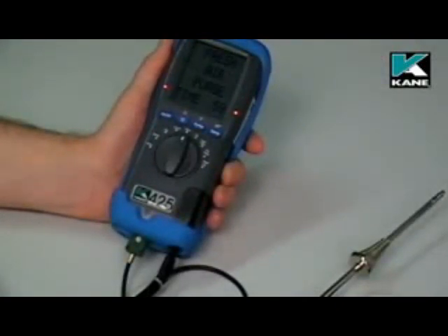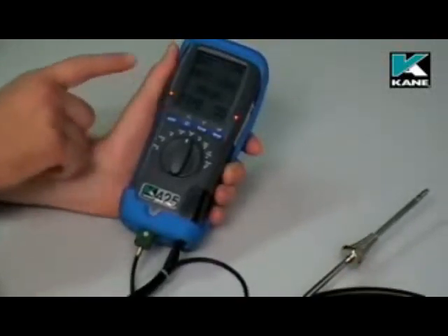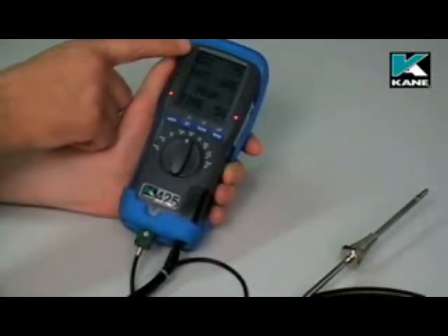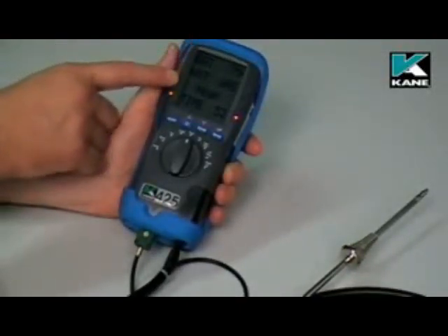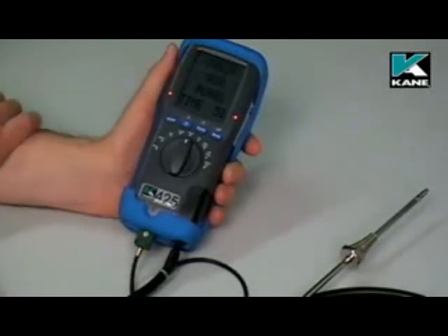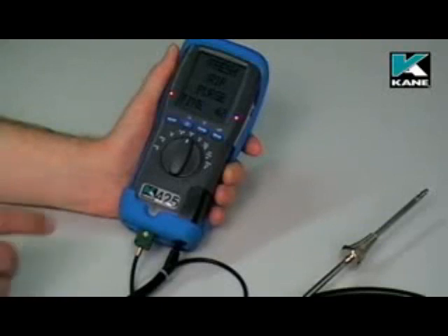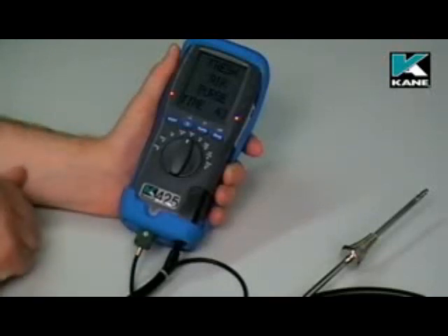You can hear the pump start. It starts its countdown, briefly flashes up the battery status, the fuel and also the pressure units, and it continues its countdown. On a Kane 425, the fresh air purge normally lasts somewhere between 30 seconds and a minute. On a Kane 455, it normally lasts 90 seconds.